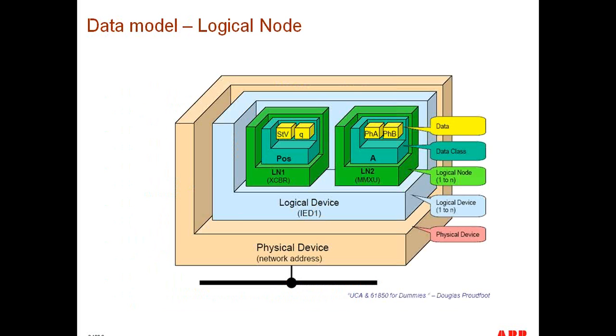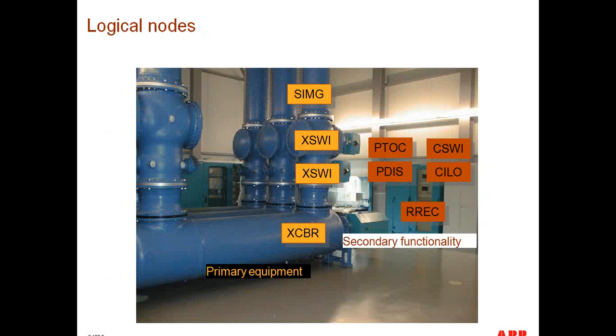And then inside each logical node or each function, there's data associated with it. So in the case of, for example, a metering function, you're going to have A for the amplitude of phase A, phase B, as a measurement of an analog quantity. In the case of this logical node, XCBR, for the representation of a circuit breaker, you're going to have data associated to that circuit breaker: health, pressure, position in this particular case we're showing. So it is a standard way of representing all of these different functions, and that is the first point that really makes the standard unique, which was not done with any other substation automation protocol prior to this.